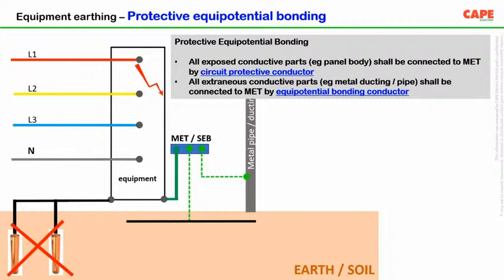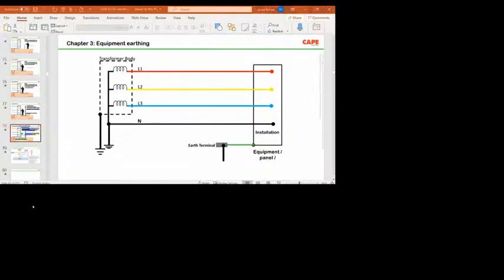Sometimes what happens, the equalization terminal wherever you are standing, if that terminal and the body are interconnected, and the person is standing over there, current will not flow, because from same potential to same potential current will not flow. So that is the most important. Keeping more and more number of earth pits does not make sense. Rather, we should understand this term, what is called equipotential bonding.